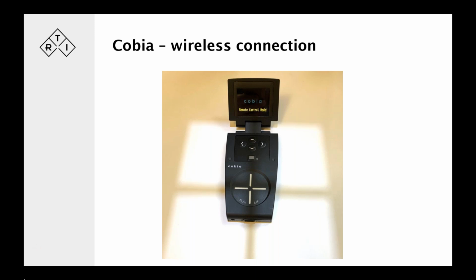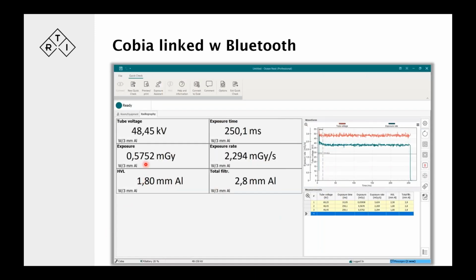There's also a possibility with the recent Cobias with the black casing. They're all fitted with Bluetooth devices, so we can have a wireless connection if you choose. Setting it into wireless mode, there's only one readout. Either it's on the display or we make a remote Bluetooth connection to a laptop running the QuickCheck software, and we get similar readings as we do from the Piranha, with the data that we're reading, kV, time, dose rates, etc., the waveform, and a log of the latest readings.